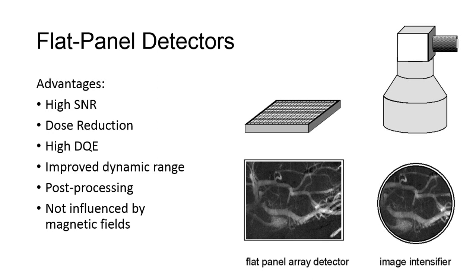In addition, flat panel detectors are not sensitive to magnetic fields, and they have a linear response that can be manipulated, like static digital detectors are for post-processing techniques. All of these features are causing the industry to quickly replace traditional image intensification systems.